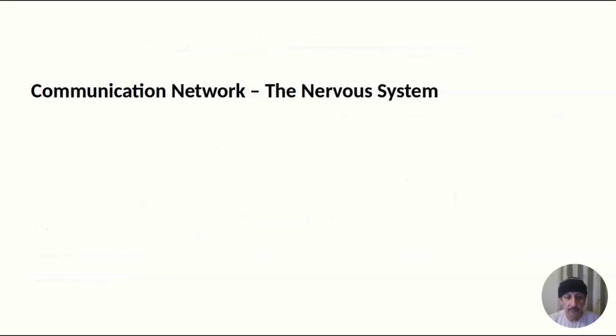Communication network, which is the nervous system of the system. The network is the lifeline of the DCS. If it fails, coordination collapses. Industrial Ethernet is now the standard, but it's not like the office Wi-Fi. It uses deterministic protocols that guarantee message delivery within strict time windows. This is critical for safety-critical loops.